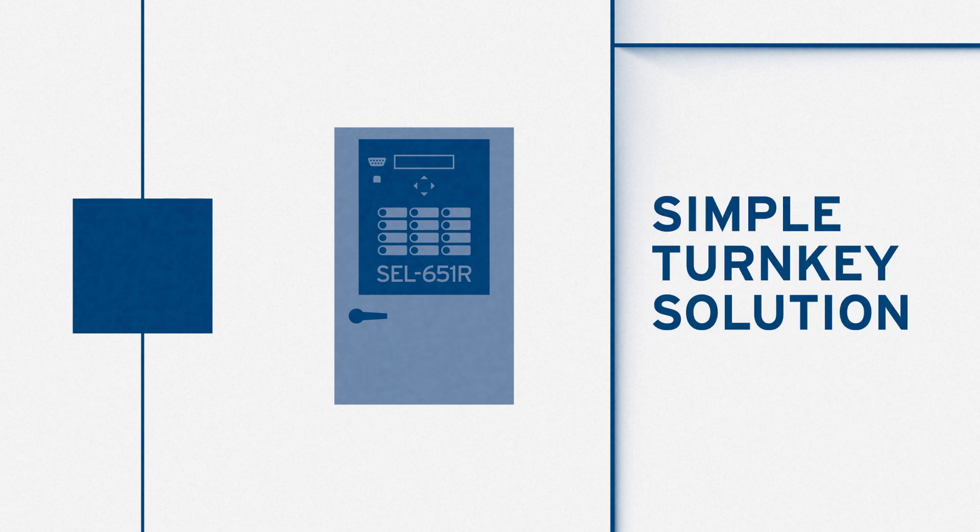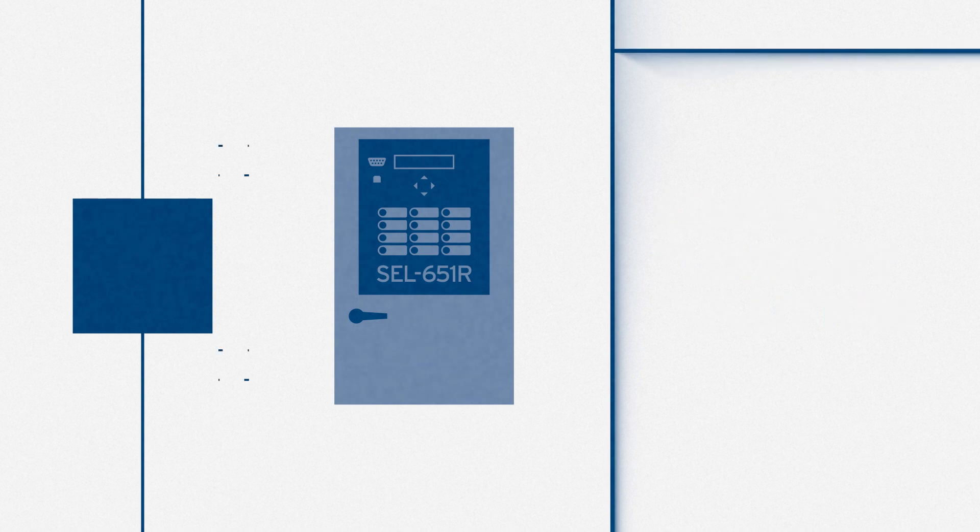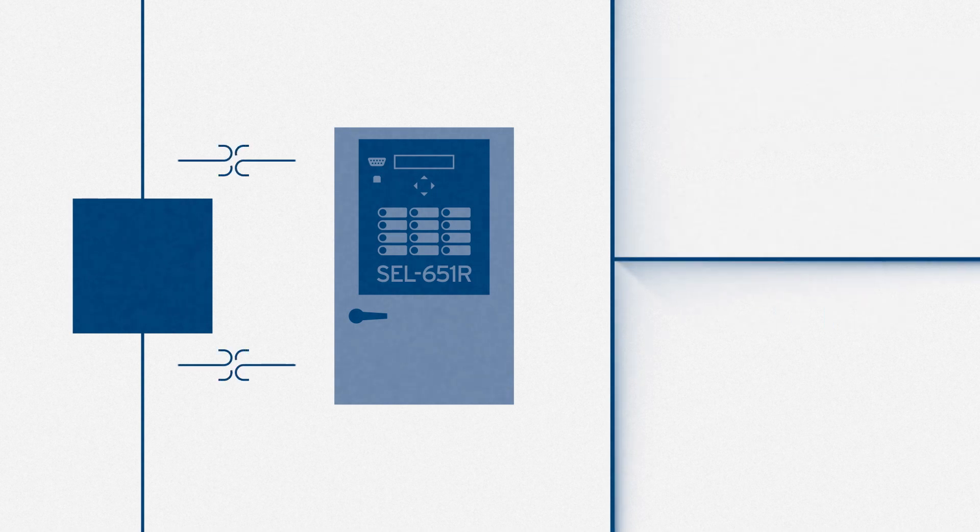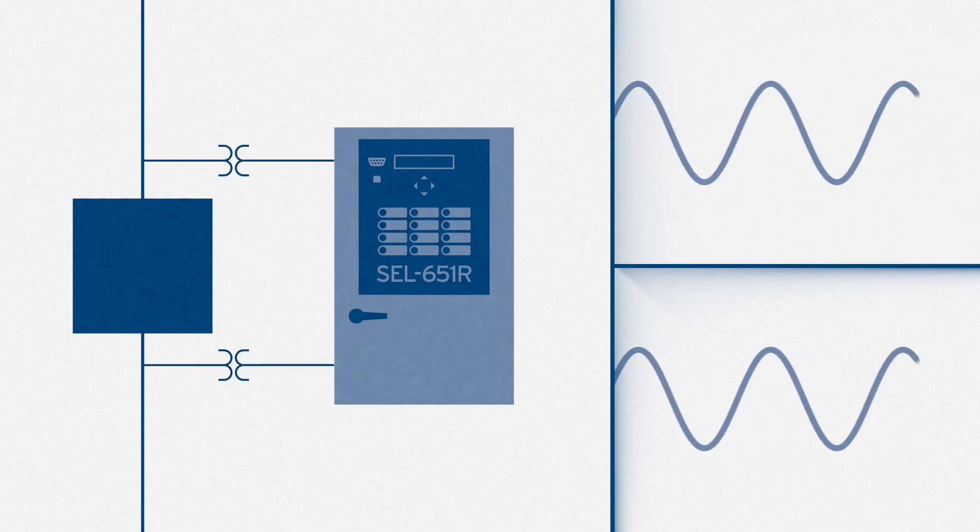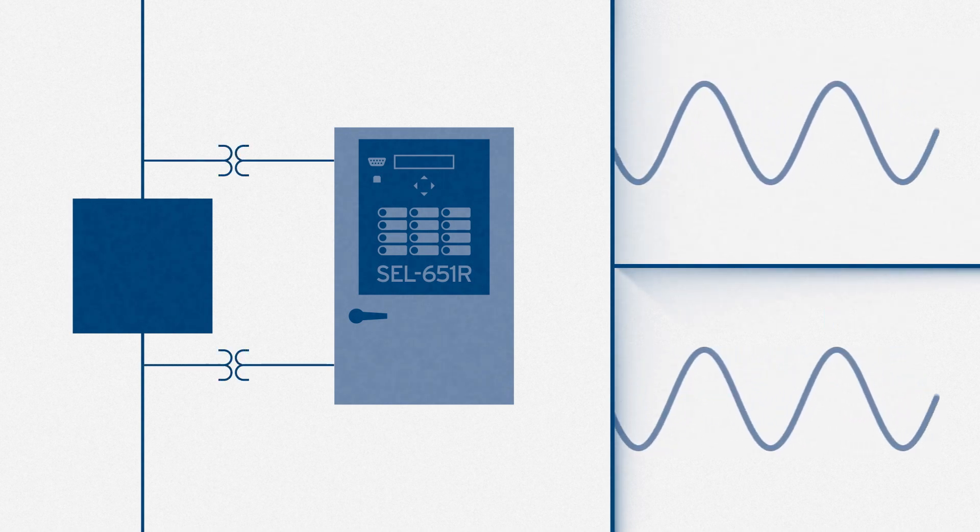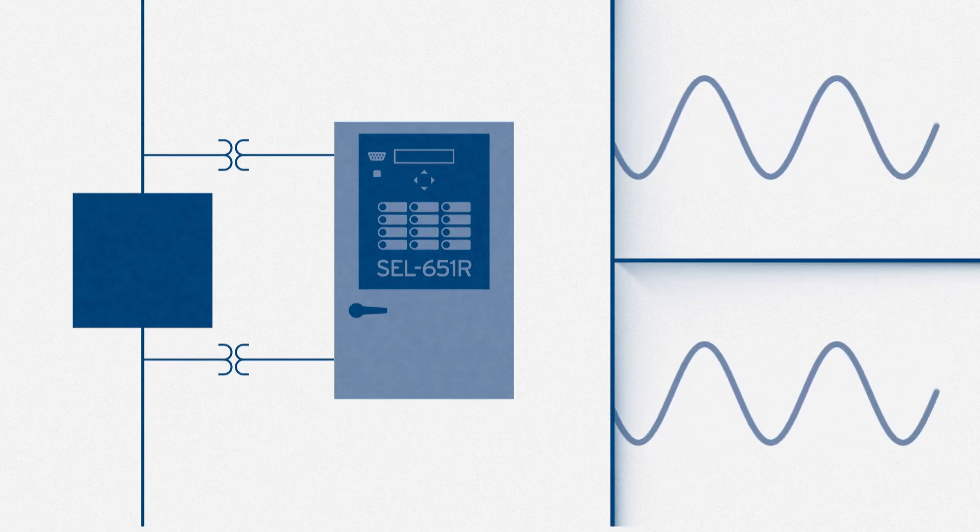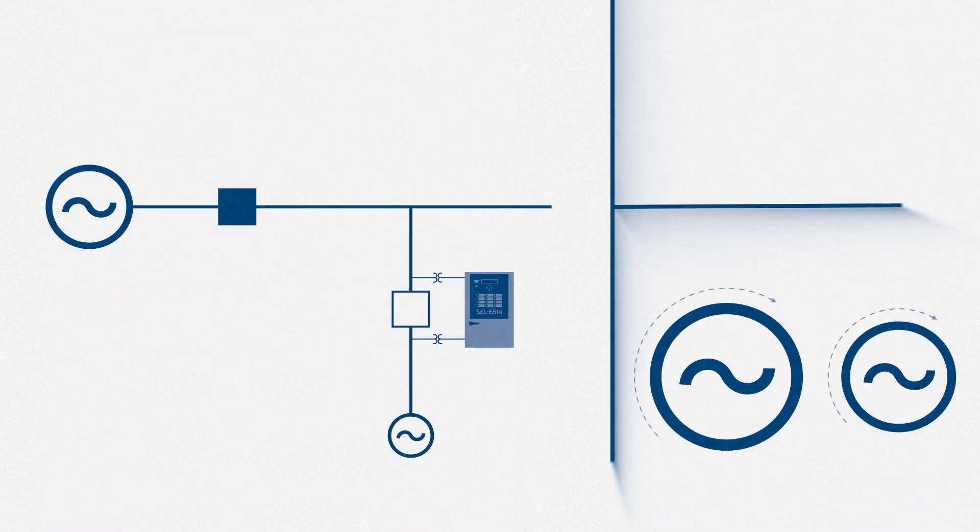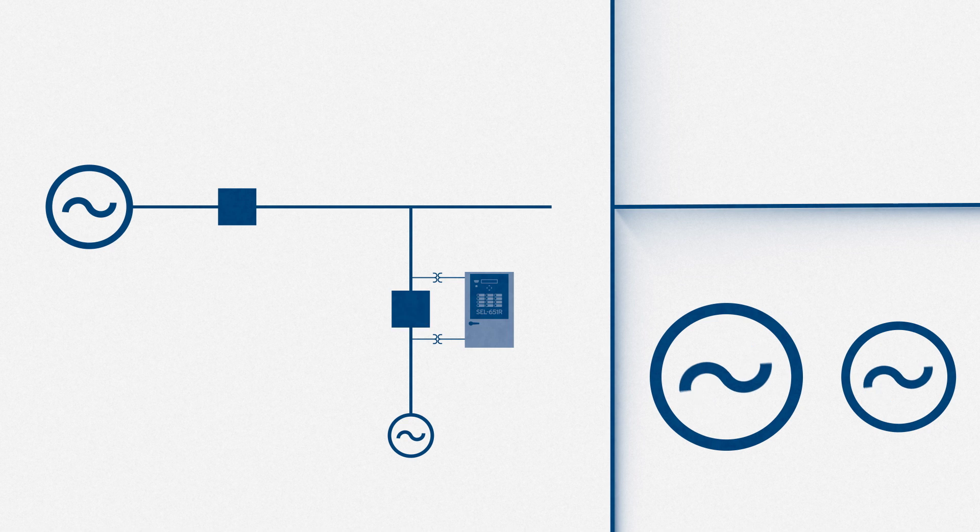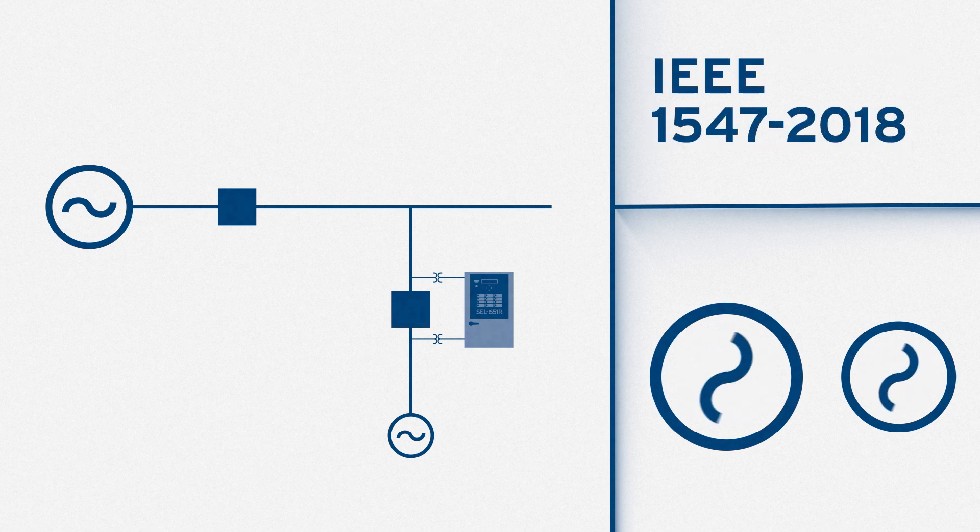Now, we've got a simple turnkey solution to connect and manage DERs for points of common coupling. The SEL651R monitors voltages and frequencies on both sides of the recloser and ensures absolute synchronization with high power quality before allowing interconnection, so it meets that latest industry spec.